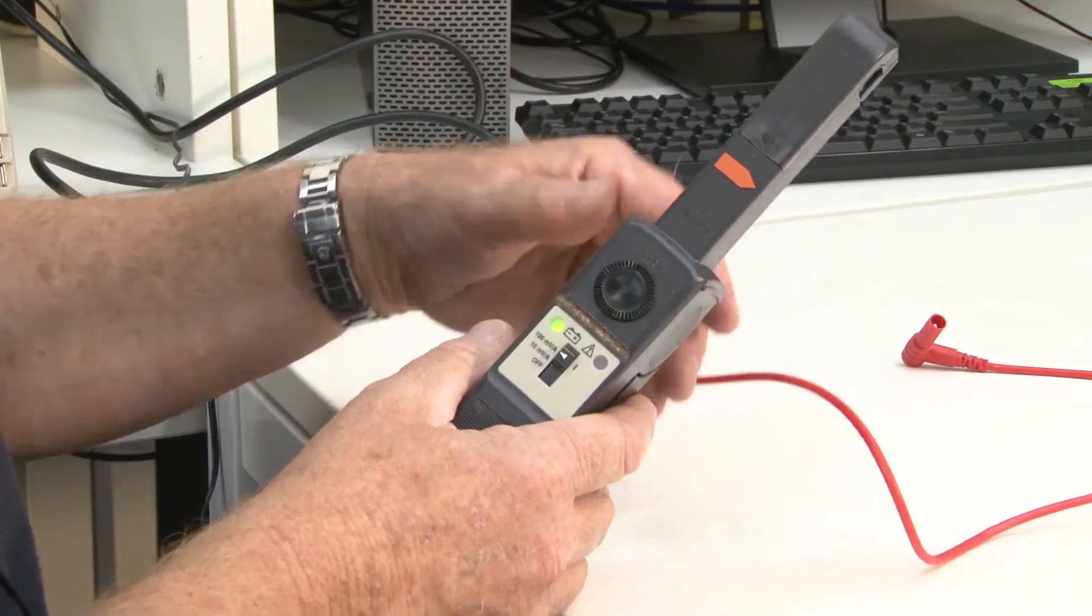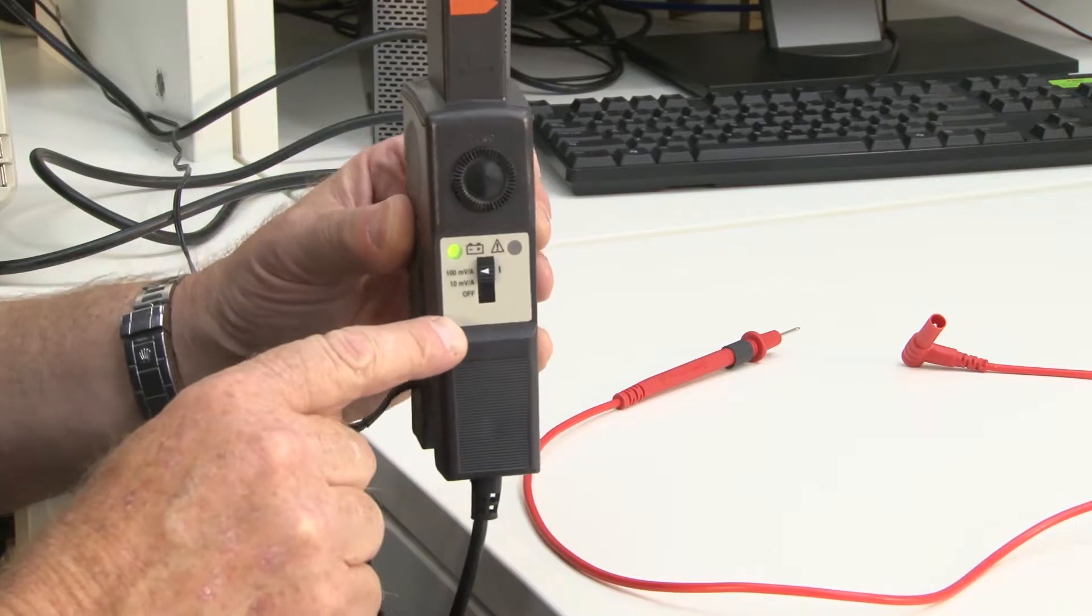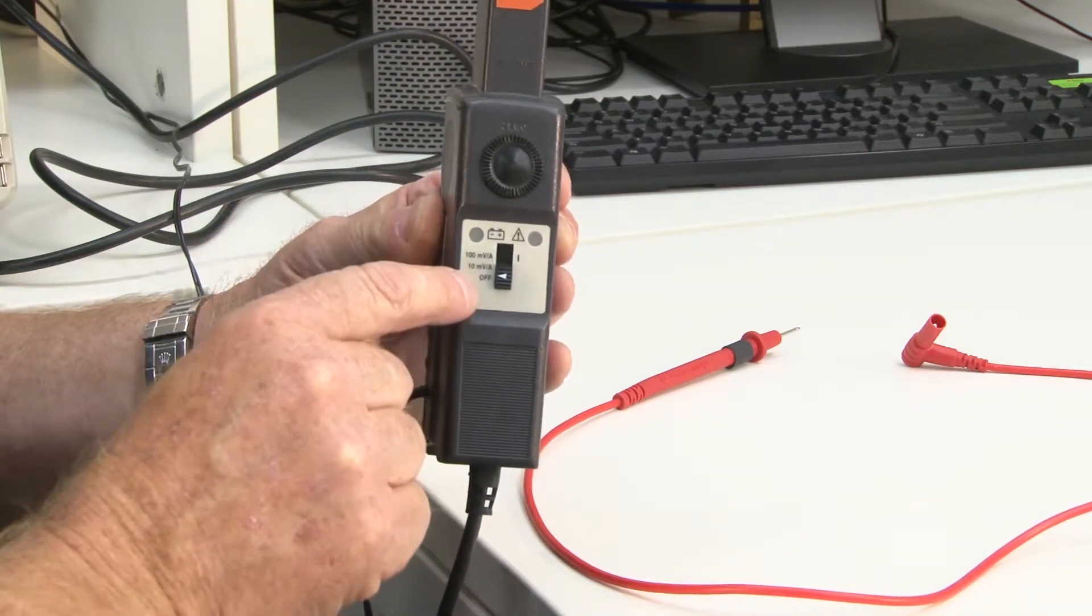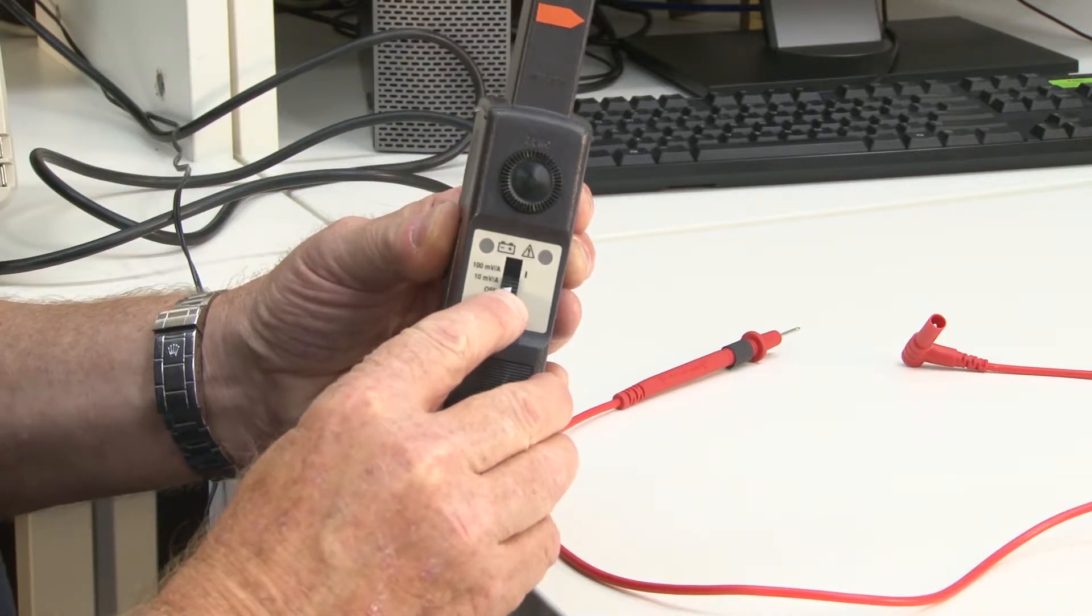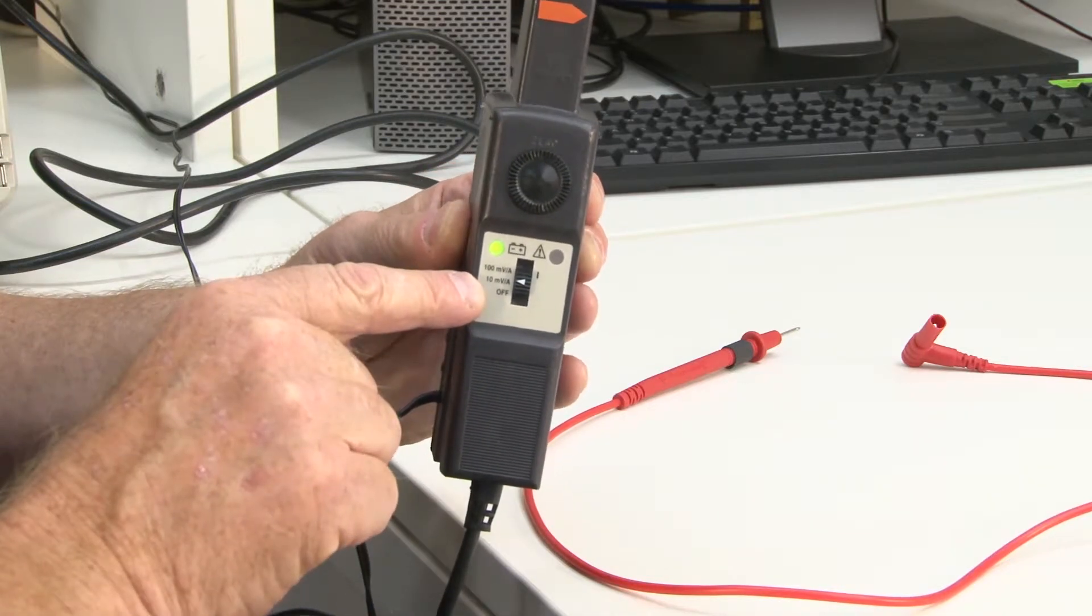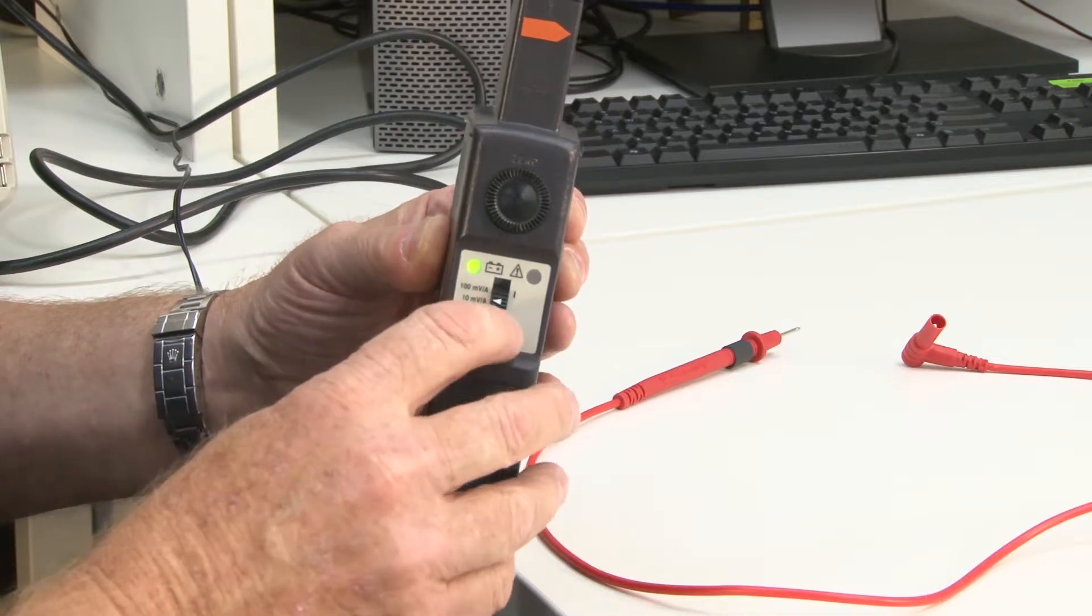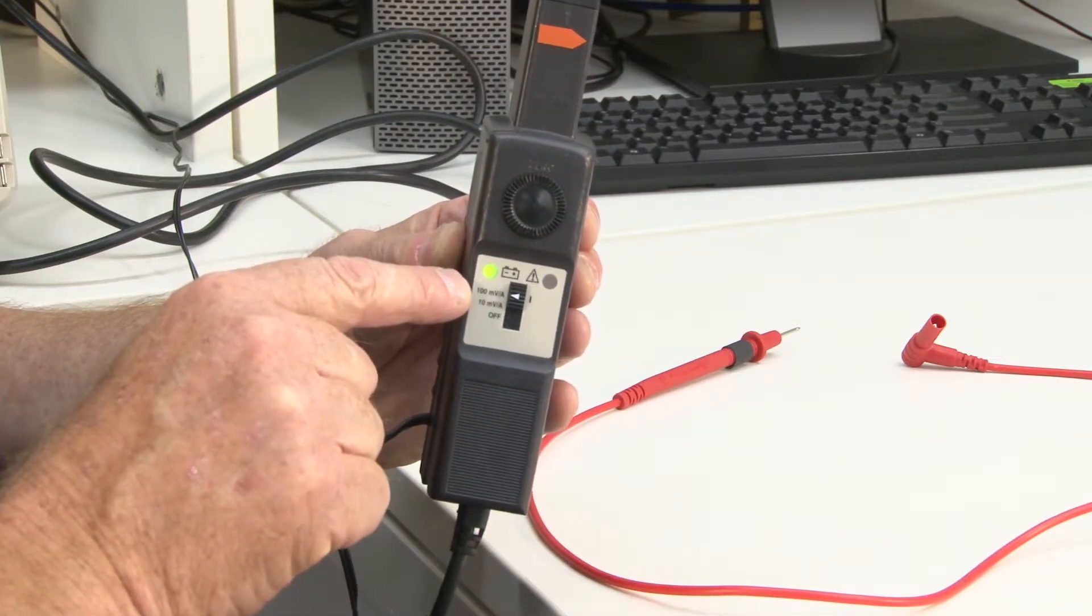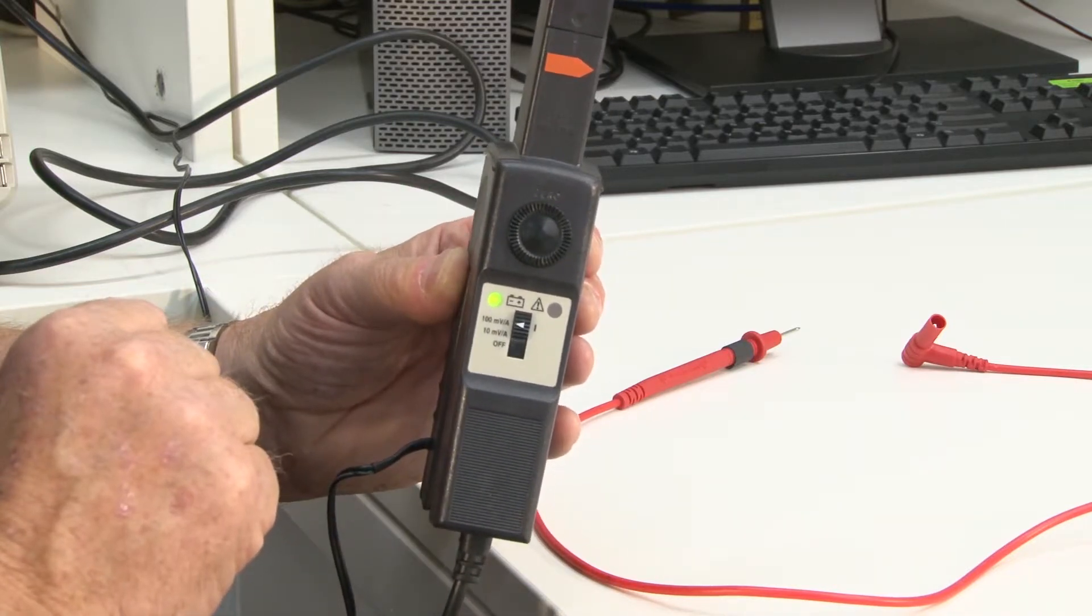Now have a look over here. What we have is a little switch here, and there are three positions. The lower one here is the off position. If we move it up to the first position here, that indicates that we're set to 10 millivolts per amp. Moving up to the top position, that indicates that we are at 100 millivolts per amp. And in a moment we need to explain really what that means.